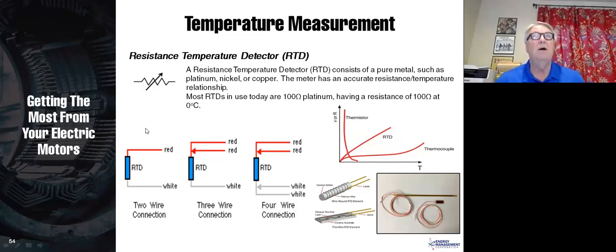I'll tell you an experience I had up in Fairbanks, Alaska. We had some RTDs, and they had wired them in this way with just two wires, but the wire was a long ways. It was probably 300 feet up to the motors, which are in a different part of the building. And they noticed that the motors were running extremely hot. I went up and measured the temperature of the motors and put my hand on them, and I said, this is not right. They are not running this hot.